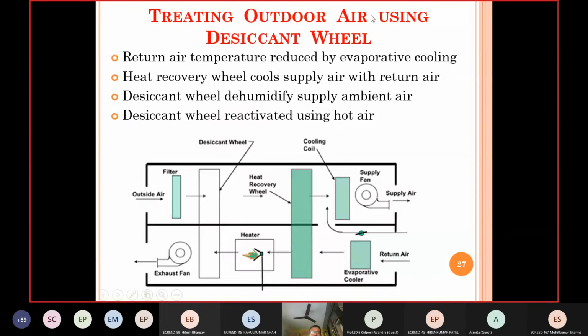Yeah. So the dedicated outdoor air system can have this kind of scheme where there is interaction between the return air and the outside air, as you can see here. So what might be done is, because this return air has low enthalpy, you would like to reduce the enthalpy of the outdoor air with the help of that. So first, evaporative cooling may be done, and so the temperature goes down. Evaporative cooling can be done here because the return air has low RH, right? You are maintaining it generally in the range of 40 to 60%. So with the evaporative cooler, you can produce a further lower temperature.